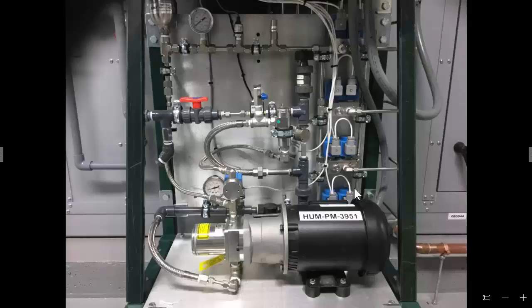Let's take the next scenario. Say this zone valve works fine, but this dump valve is stuck closed. It's normally open, and let's say it sticks closed. First off, it wouldn't cause any alarm. The purpose of that dump valve is to relieve high pressure from this line, which goes out to the nozzle, back through the valve into the dump side to go to drain. The purpose is to relieve the pressure within the line out to the nozzles so it prevents any dripping. If it does not open up, high pressure would stay in that line and it would bleed down a bit to what the internal check valves within the nozzles are designed for, and it would just stay at that pressure. So it would not really cause any alarm.